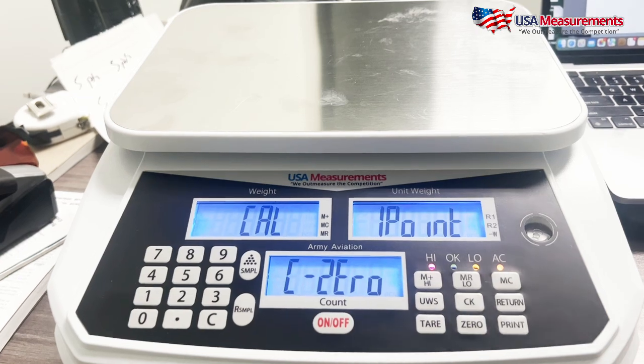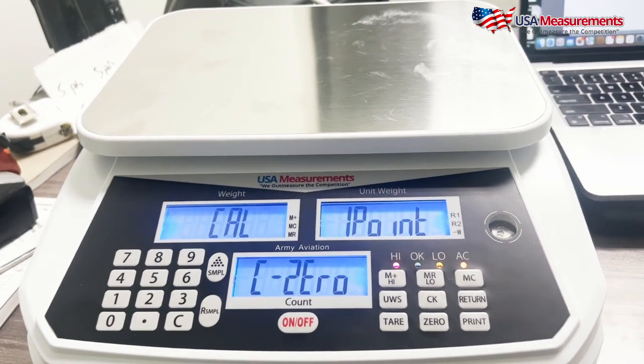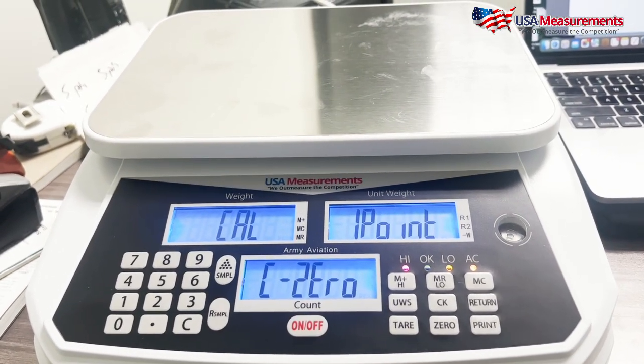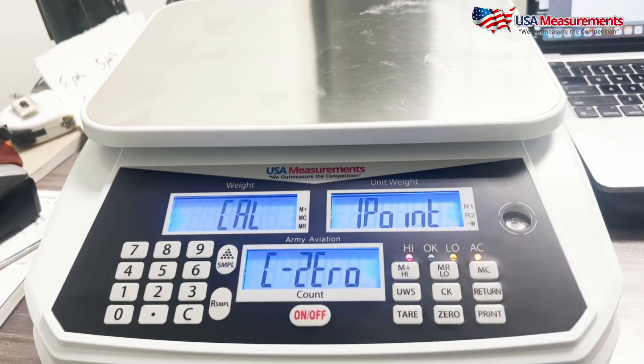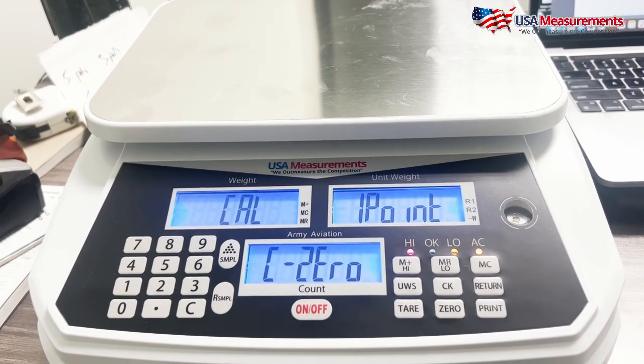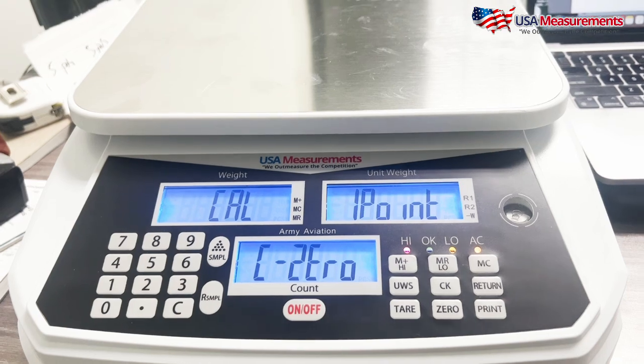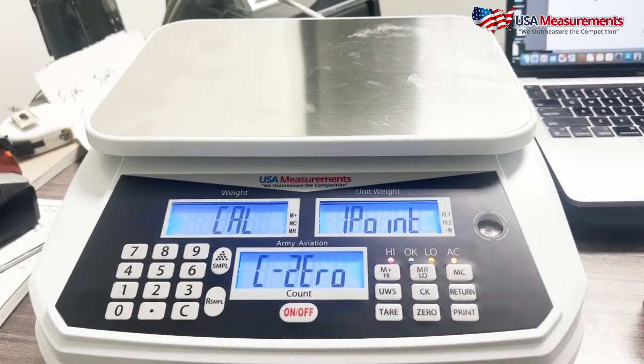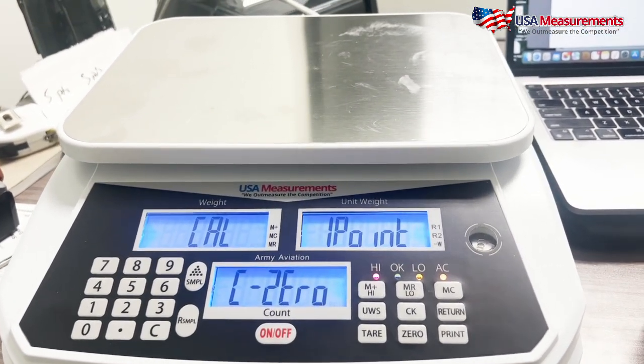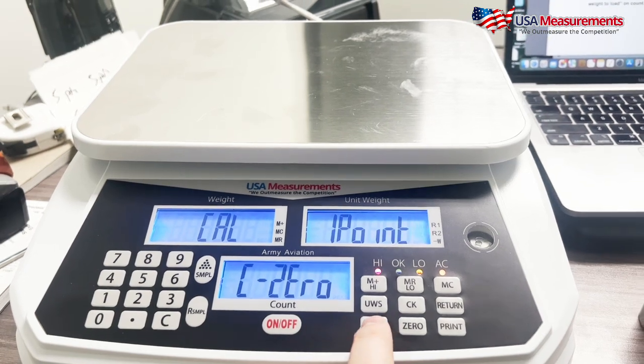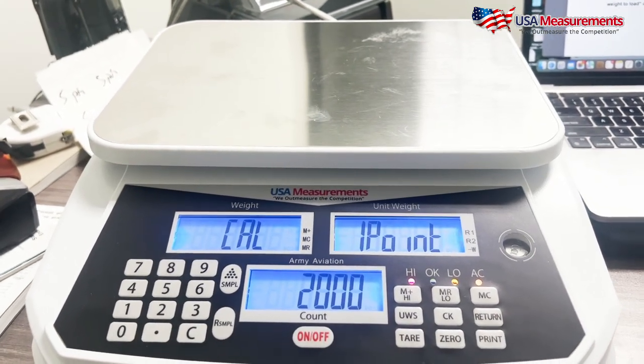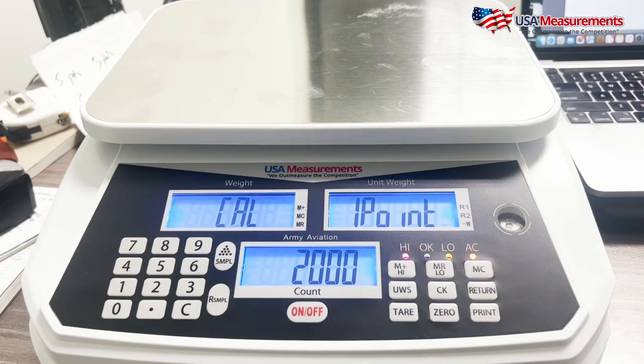Now you'll see cal on the weight screen for calibration, 1 point in the unit weight for calibrating a single point, and the C-0 on the count screen, because at this point we're going to be calibrating our 0 point. Nothing should be on the scale. Once that is clear, you want to hit the tare key. Once that's tared, it'll now show a value in the count screen.